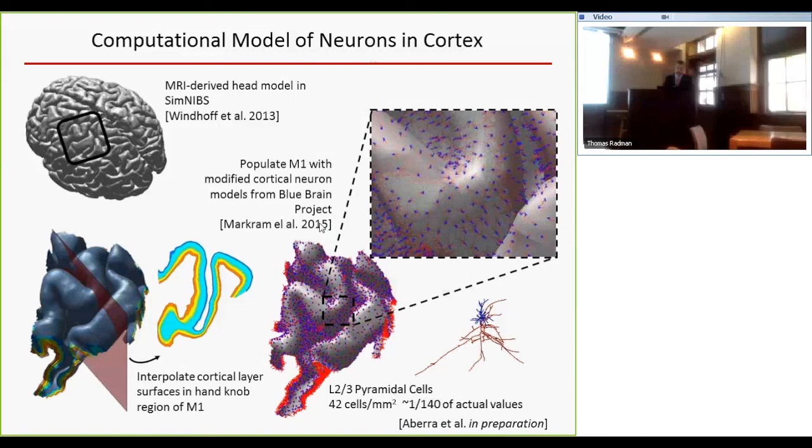And I wanted to point out that for those of you who appreciate pulse amplitude in terms of amperes per microsecond, which is one way in which you quantify pulse amplitude, for example, the MagPro device will give you that value as a measure of amplitude. These values, the lowest value here, are on the order of 60% of the conventional device output.